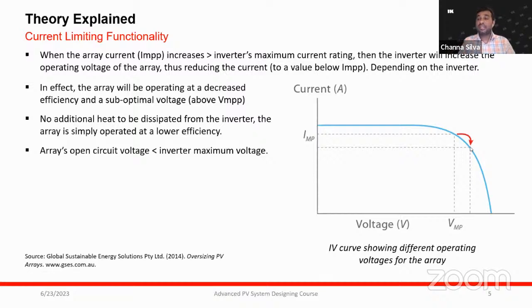the inverter. But before you do oversizing, first look at whether the inverter can accommodate some sort of standard test condition or rated power of this much power at the inverter's input. If so, when you're oversizing, the inverter has a facility to bring down its efficiency to a certain degree and adjust the operating point. But again, it will reduce some power because it cannot take the same current input, so the power will be reduced. And since the inverter can accommodate that, there will be no heat dissipation because it's lowering the efficiency.